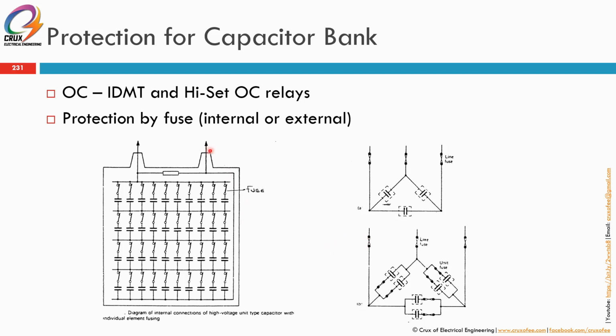For protection of the capacitor bank against overcurrent, we may use IDMT and Hi-Set overcurrent relays, or we can also use protection by fuse. Internally in this capacitor bank there is a fuse, in fact a lot of fuses. All these fuses will melt once overcurrent happens within this capacitor bank. As you can see here, there is one component, which is actually the internal resistor of the capacitor bank, or the high voltage unit type capacitor. This is to discharge the capacitors once you switch off the capacitor bank. Normally you have to allow 10 to 15 minutes before this resistor successfully discharges all the remaining stored charges within the capacitors.